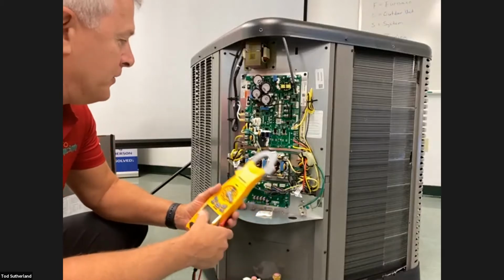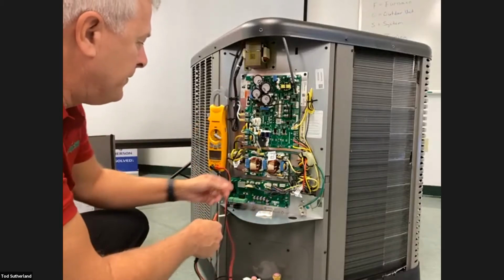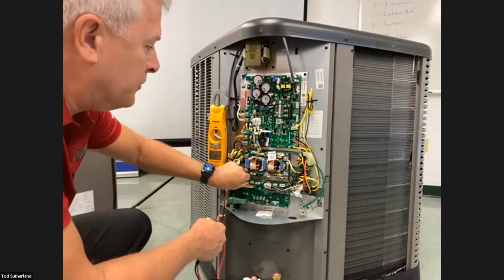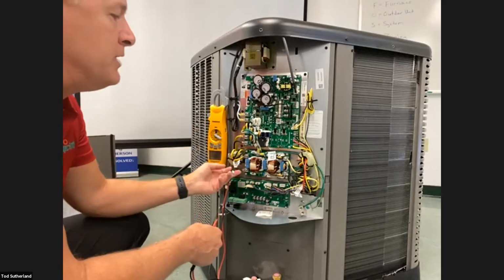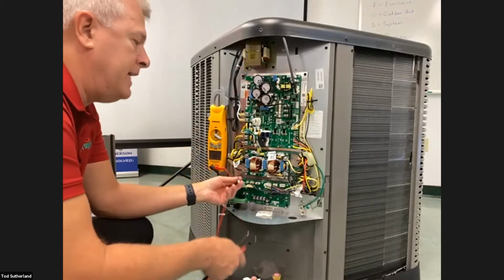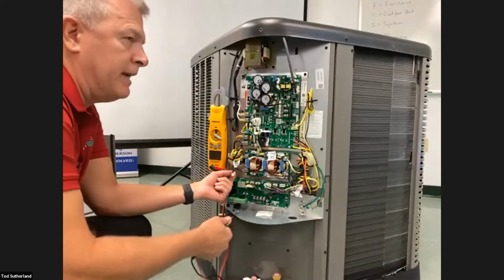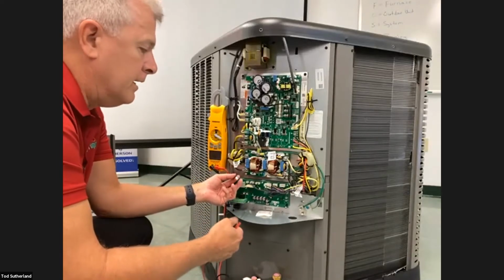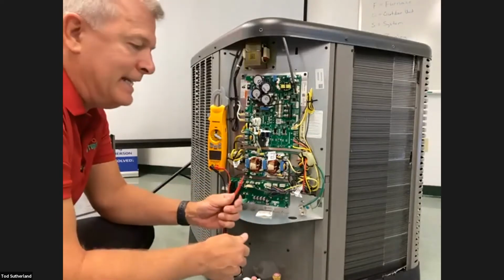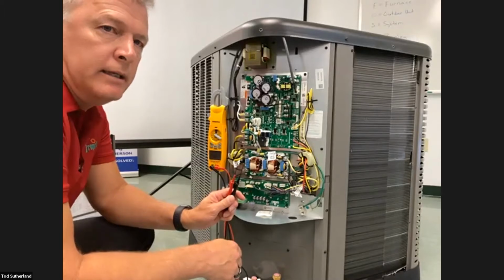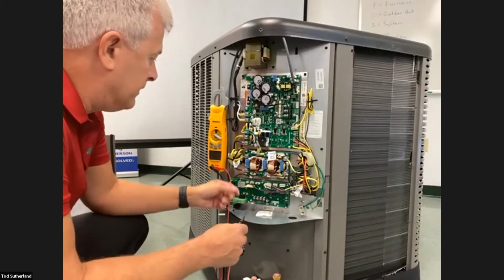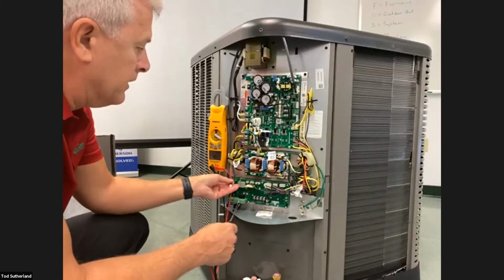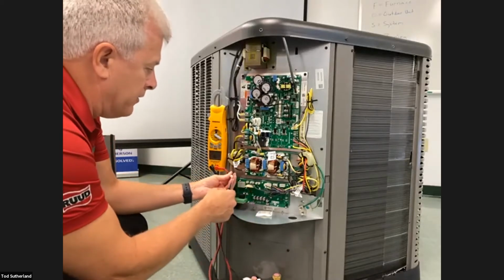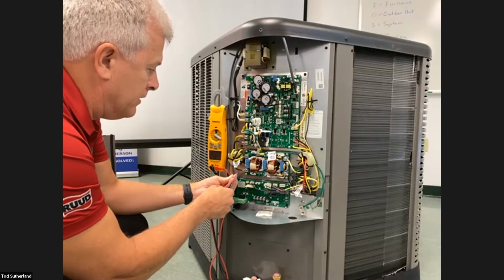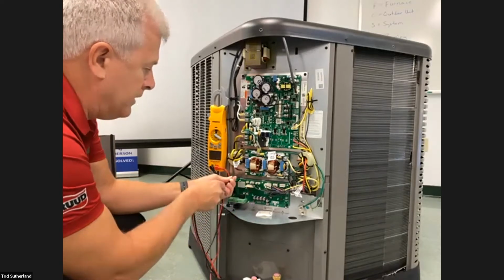But you'll put this on your ohm scale here. You can remove these plugs. You do not want to ohm these out while the plugs are attached, because you'll not only be reading the resistance of the thermistor, but any resistance you're picking up through the board. Okay. Then from there, you're definitely going to need needle point probes. These come with the meter. You're going to take these and insert those into the end here.